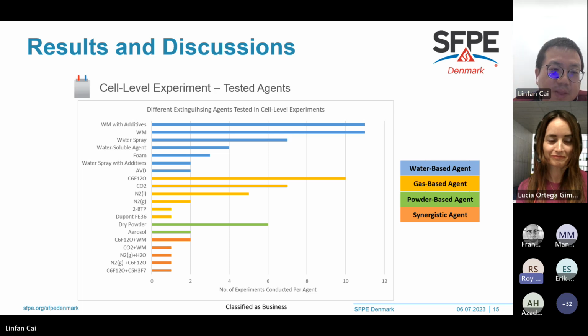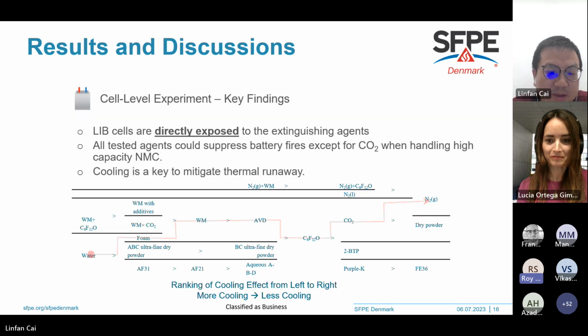When I was looking at the chart you had, I understand why Novec is being used in many cases. It's a water-free alternative, but I saw that it came off halfway in the cooling spectrum between water and dry powder. So would you say that Novec doesn't really have as high a cooling effect as Novec themselves claim?